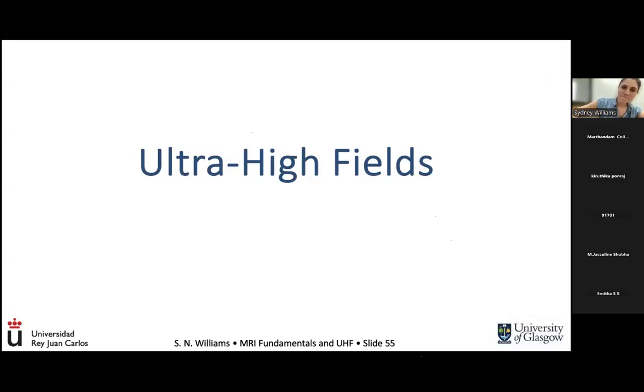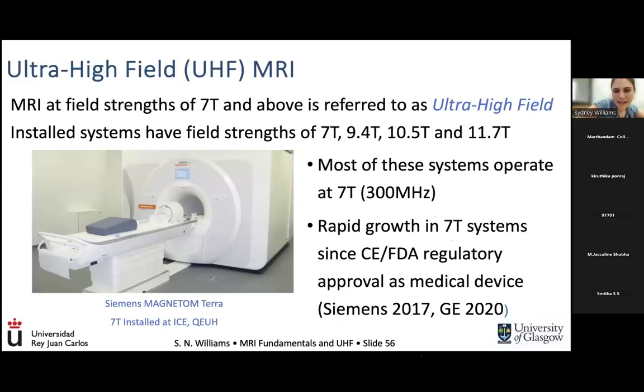Ultra high field MRI is just the category of the field strengths of MRI. So anything above 7 Tesla, and now there exist even higher field strengths, would all be called ultra high field MRI. This comes from the actual resonance frequency: 7 Tesla is categorized as an ultra high field because it's about 300 megahertz. So that's the cutoff for ultra high, and that's where we got this name of ultra high field MRI.